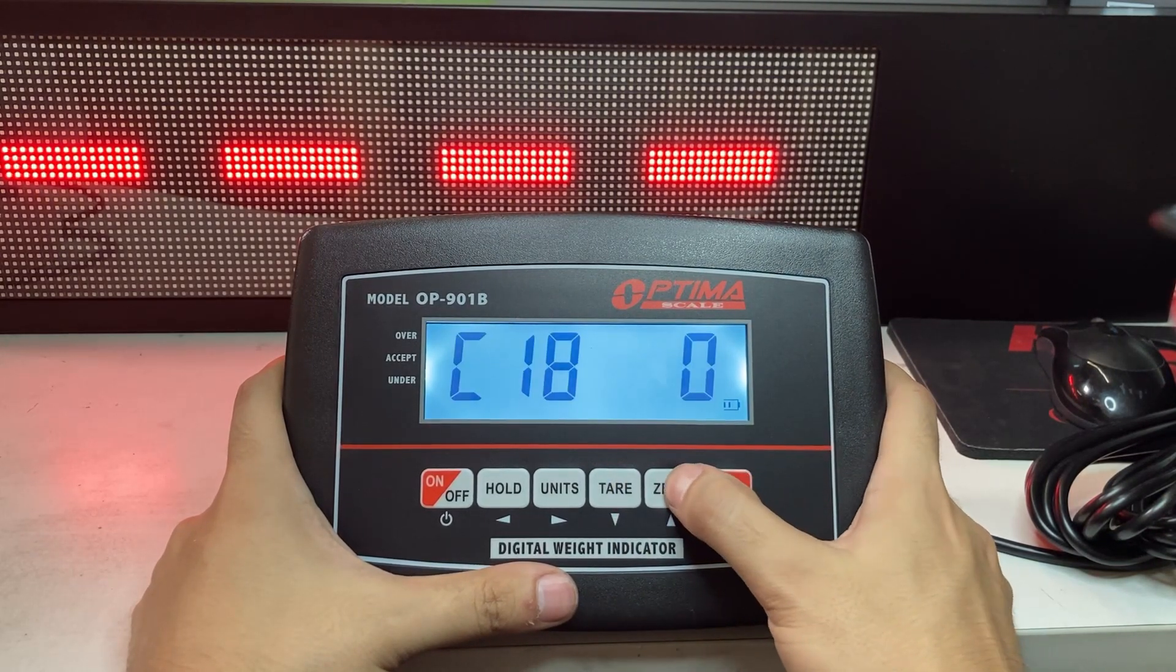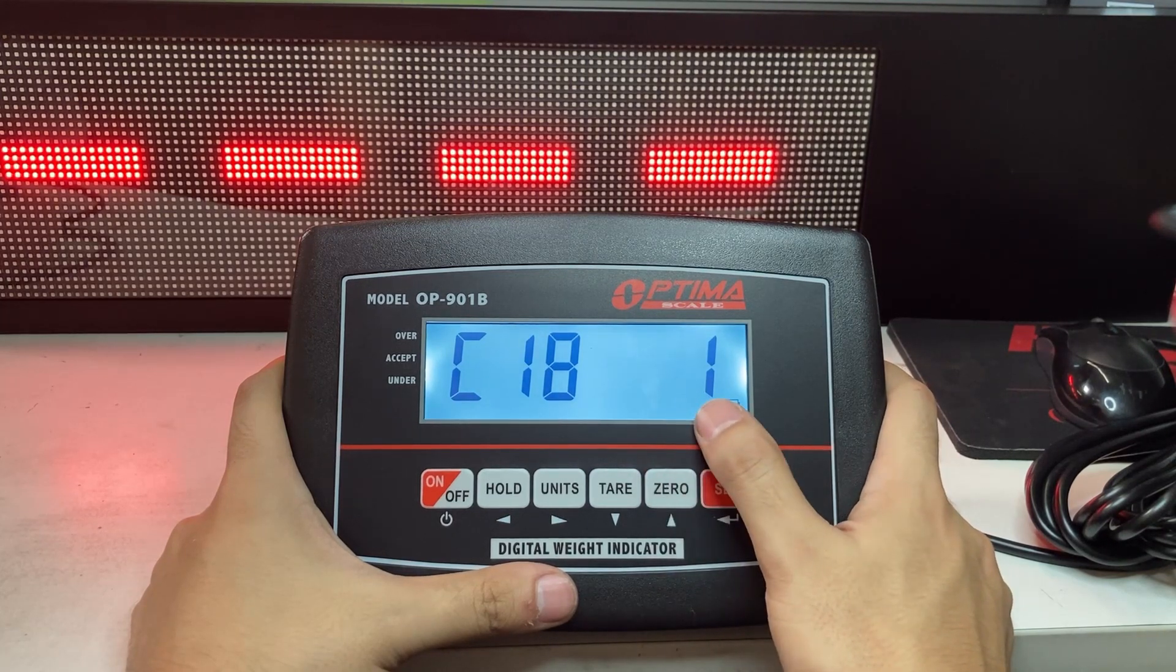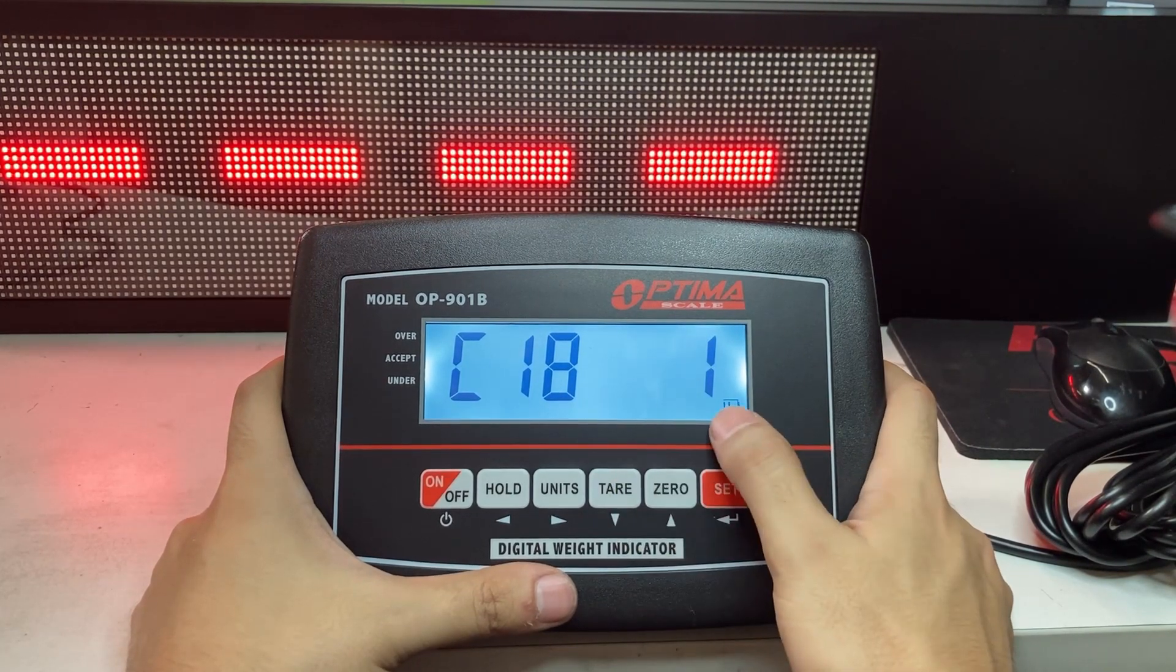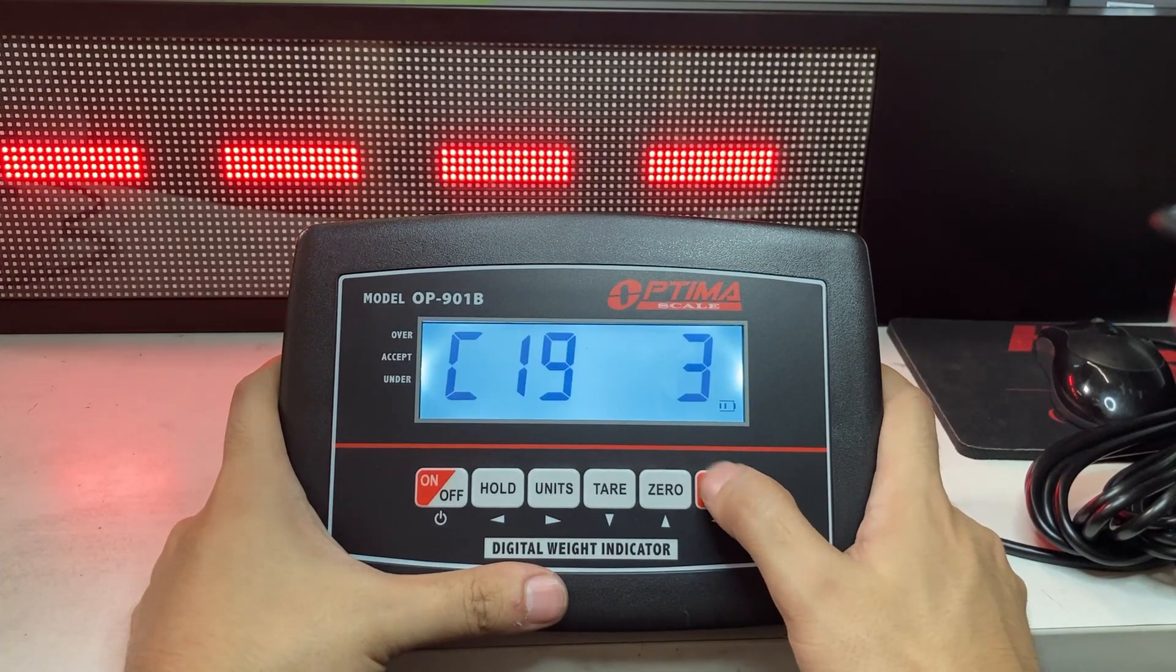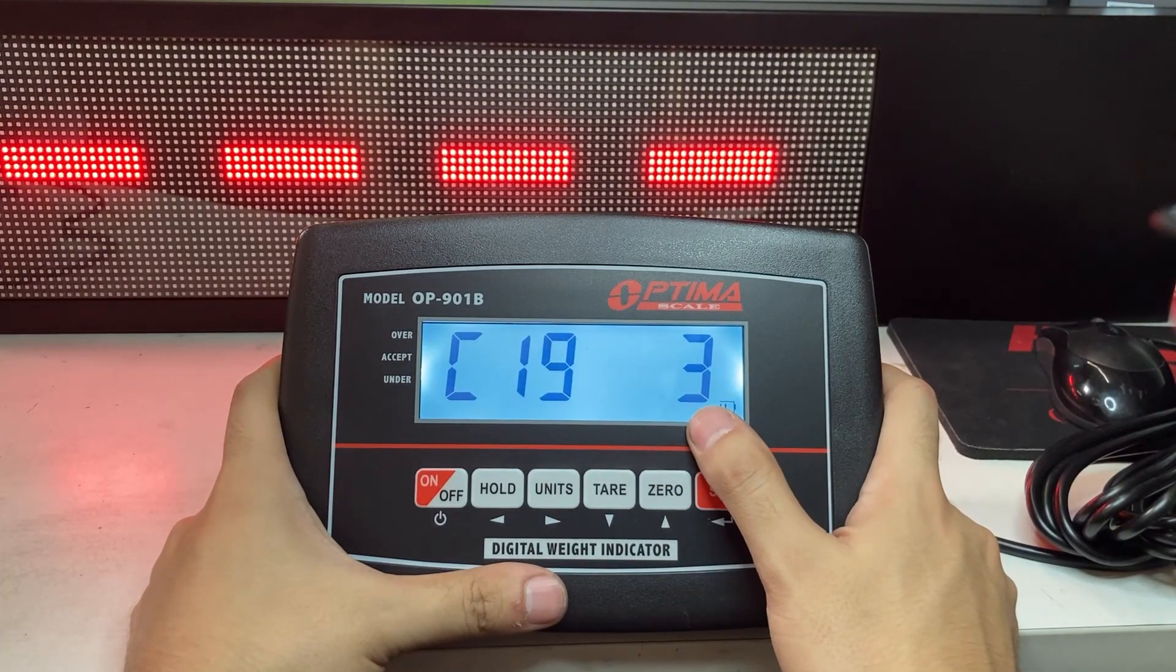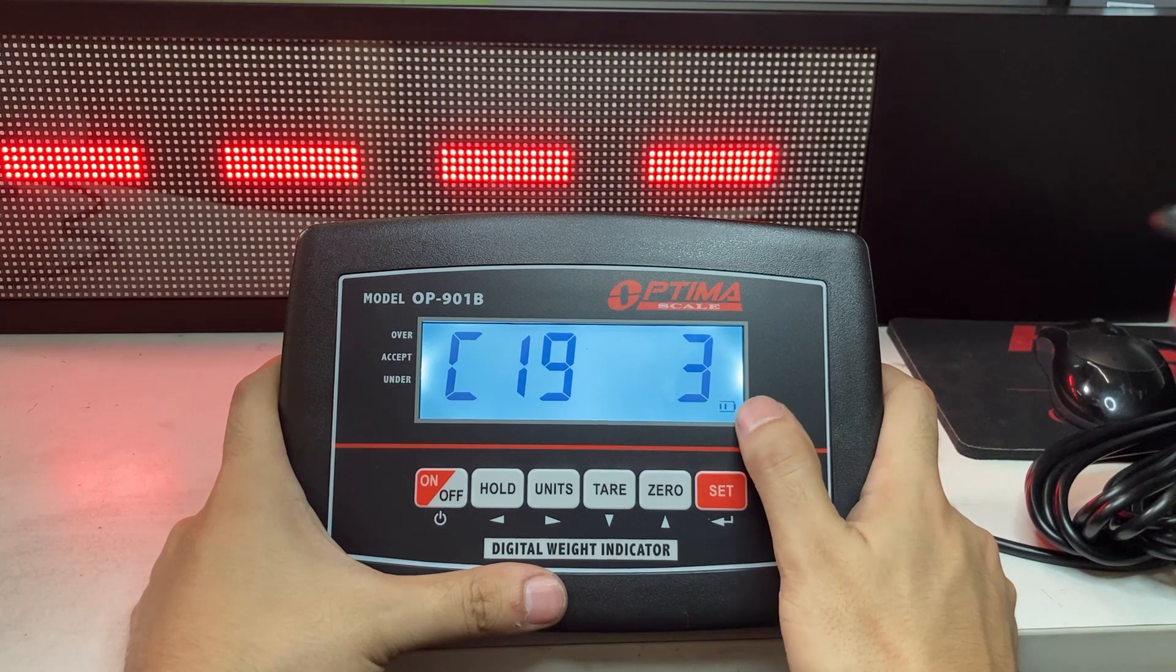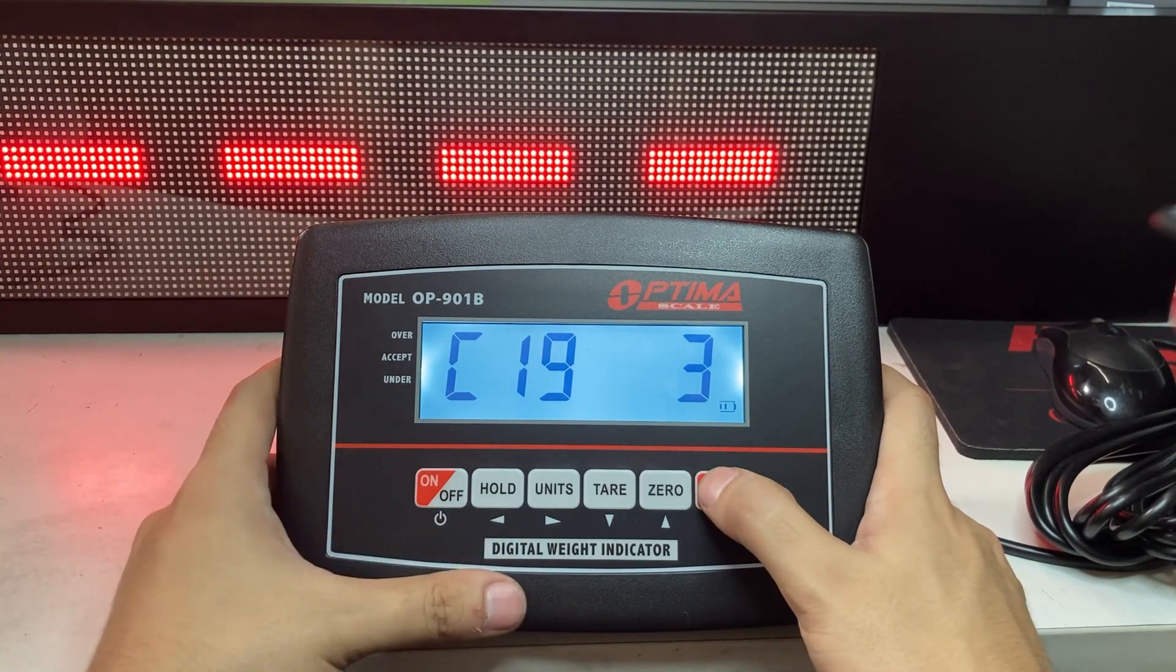For remote display, C18, 1. Press the 0 button, make it 1. And C19. We're going to set C19 to 3 for 9600 baud rate. That's for the 910X.